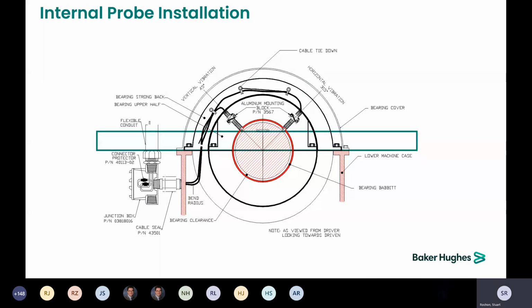Proximity probes for radial vibration generally get installed in two methods. One is an internal and the other is an external mounting. Internal mounting is usually inside the casing and uses some sort of bracket to hold the probe to the bearing cap or the bearing face. Having the cable tied down every 12 to 18 inches does keep the cable from flopping around, getting physical wear, and also picking up stray current and inducing an electrical signal that is not vibration and giving you an erroneous signal. So making sure that those are tied down can be very important.